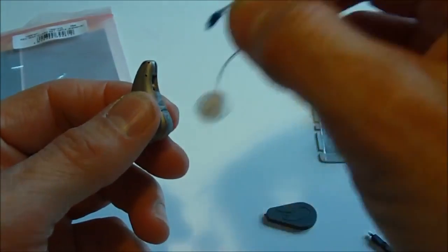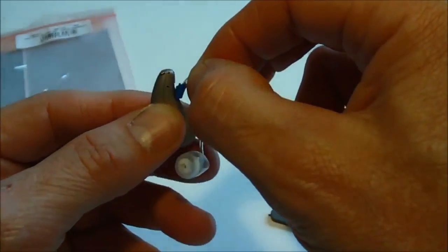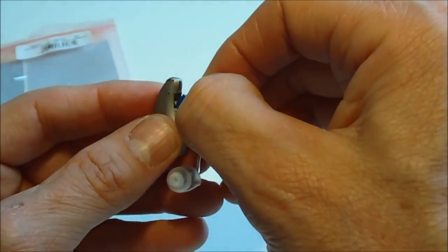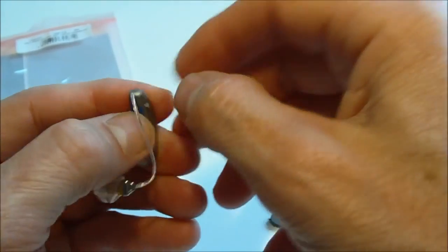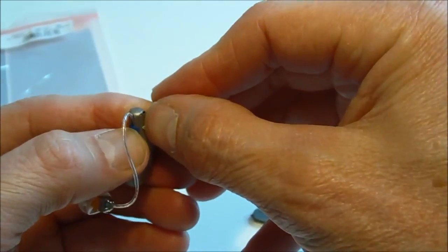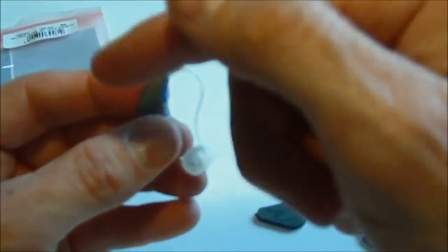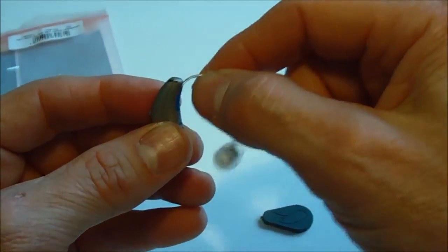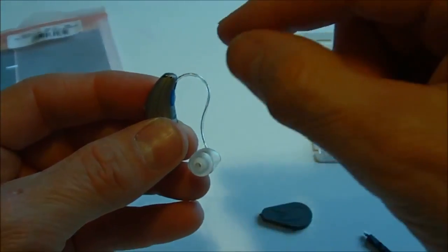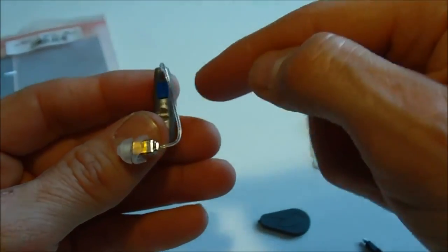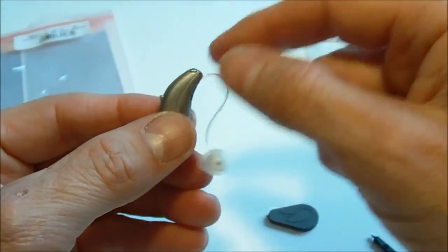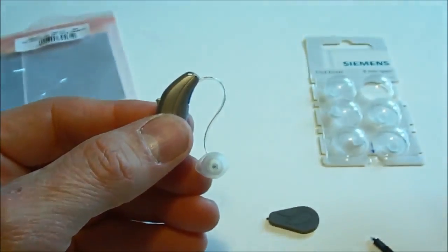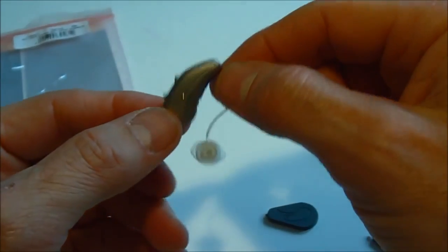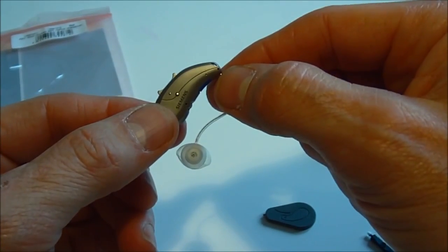If you want to check if the hearing aid is working or not, you can swap the wires over with the other side, put it back on just by pushing in and pushing that in from the other side, and then that will hold it in. If the hearing aid starts working, then you know the speaker wire was the problem. Remember to swap back, because when we program these hearing aids for you, they are programmed as a left and a right. So there you have a Siemens Pure digital hearing aid.